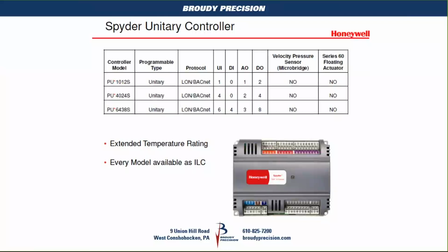The one particular unitary controller that's not showing up here is the Spyder Relay. That came out a little bit later. It has the dedicated onboard relays for the digital outputs rated at 4 amps AC. And that would have an SR on the end of it. And it has to be purchased for the 6438S. So the Spyder Relay flavor would be the PU6438SR.